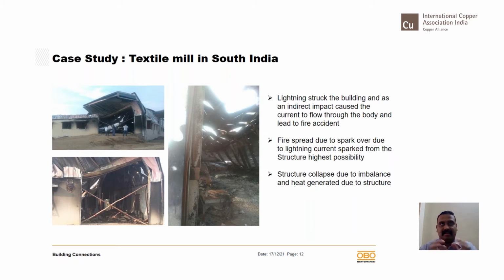In this building, yes, there was sheet metal, and there were beams and pillars in metal, so this could have been considered a natural component for bringing down the current. However, when the sheet and the beam column were connected, there were some gaps in between, which did not get properly equipotentially bonded. So there was a strike on the sheet. The sheet was punctured. There was a flashover which jumped inside, and that sparked the cables which were running on the trays around the building. The insulation of the cables caught fire, and this insulation completely carried the fire inside.